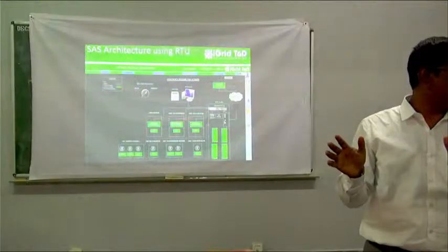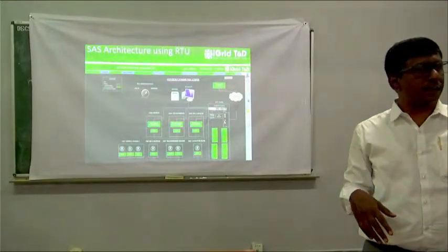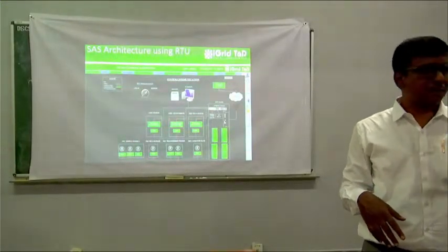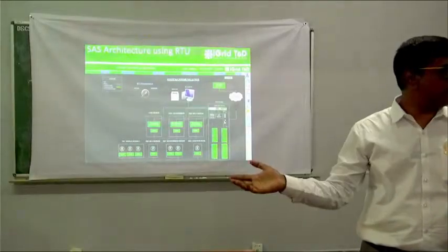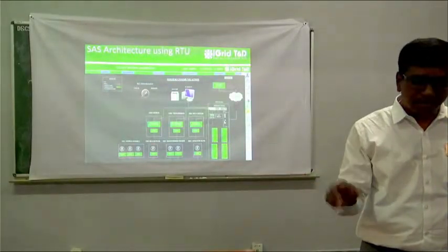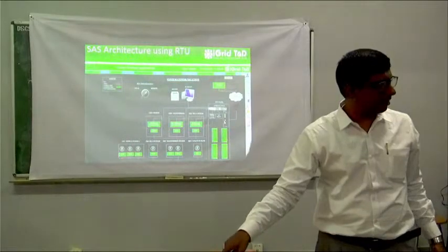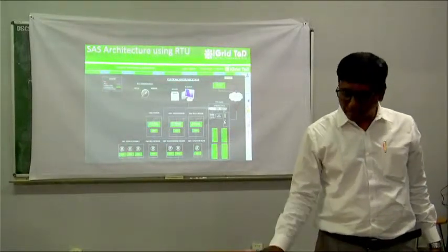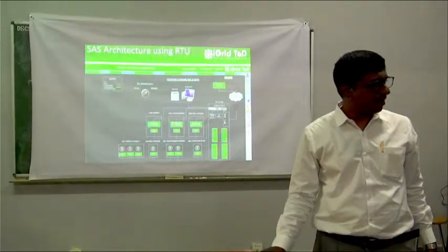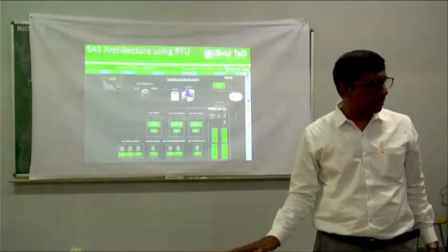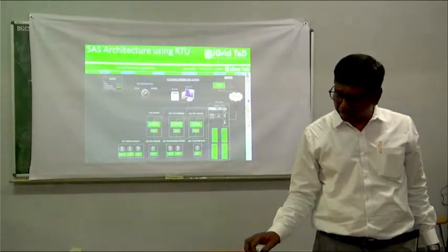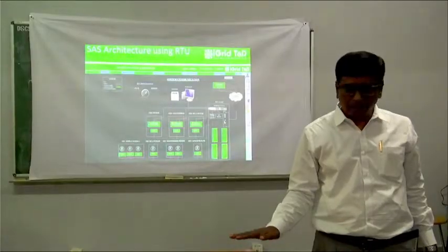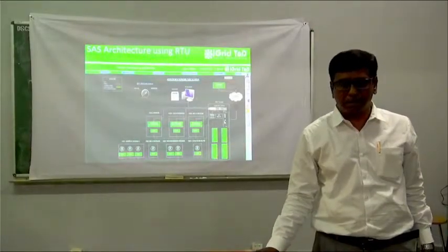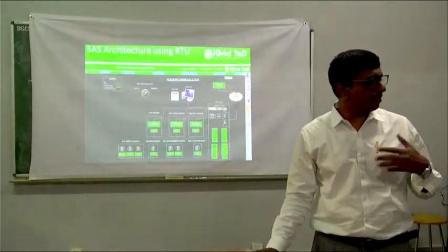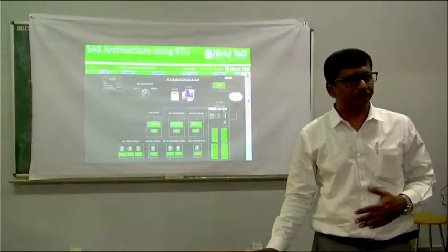Now, to avoid all these things, what I do is I give one RTU panel. Whatever existing wiring is there through contact multipliers from the control and relay panel, I get it to my RTU panel, and within the RTU panel I connect it to these contacts. Using these contacts, I connect this to SCADA, and this can communicate the data to the SCADA. Now in SCADA, I can read the status and show it. So that is how we are giving solutions to legacy substations where there are no numerical relays for communication.